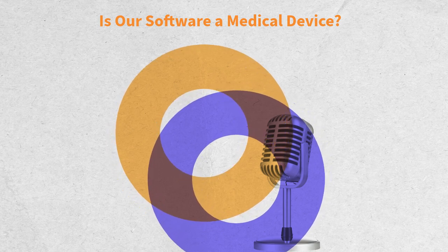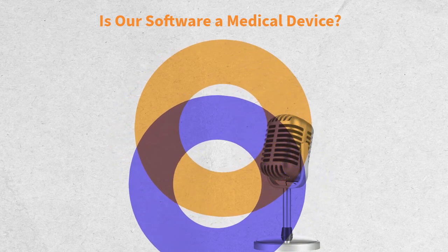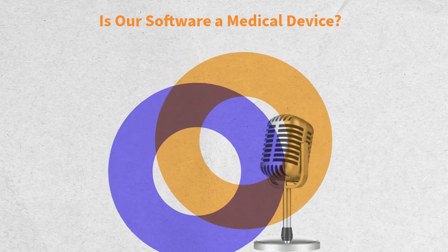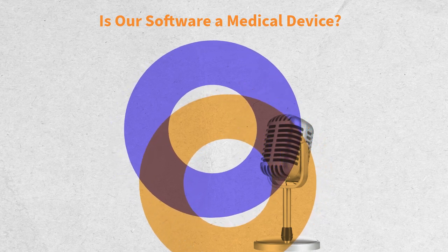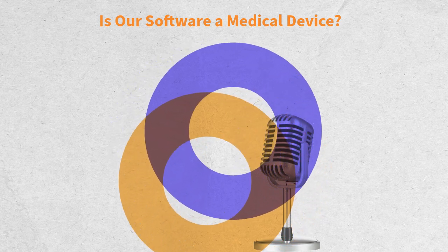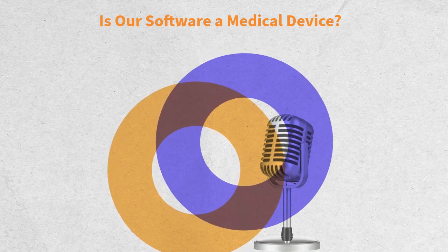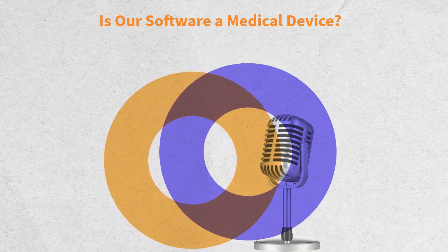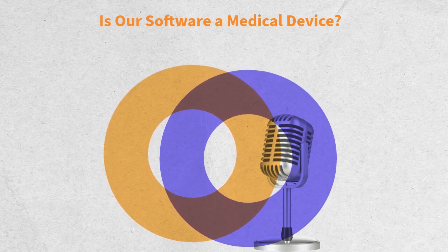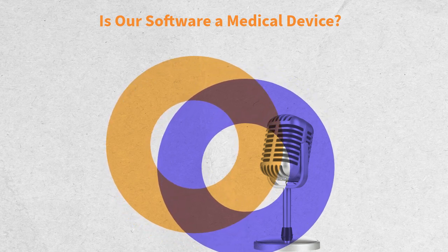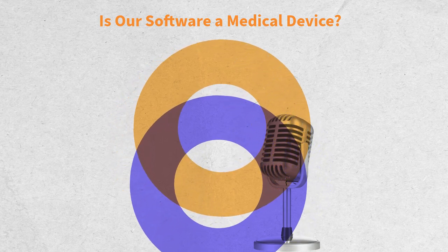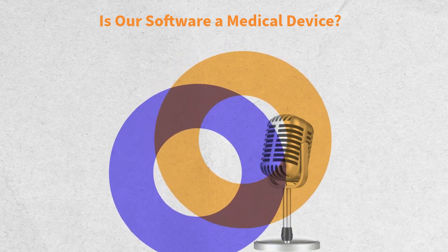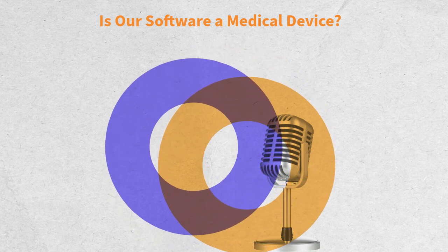When is a software considered as an accessory and not as a medical device? This is an interesting point. A software can be catalogued as accessory when it does not perform an autonomous medical function directly, but it helps a main medical device to work properly. Here are some practical examples. A tool calibrating the parameters of a mechanical ventilator. It is an accessory because it does not process clinical data.